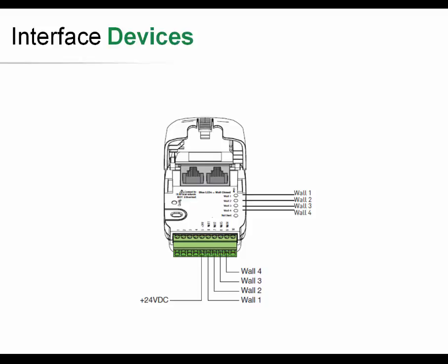The LMIO-102 has the ability to take in 4 different inputs to trigger a total combination of 16 different scenes. As these inputs are triggered by some sort of mechanical switch in the space by the partition, it'll rearrange the bindings and trigger different profiles. So here's an example of the wiring of the LMIO-102.